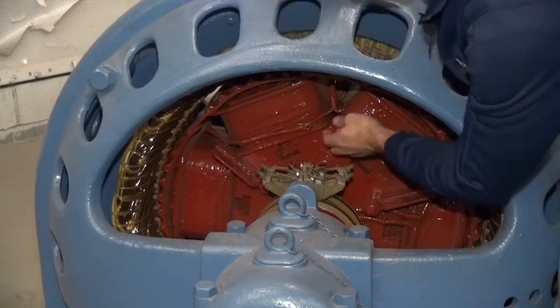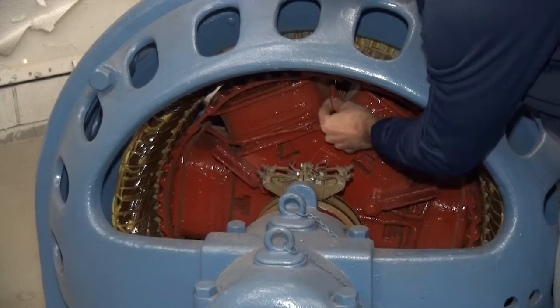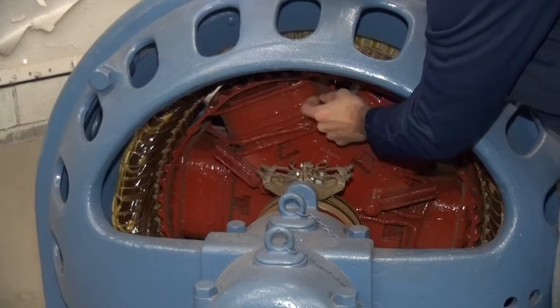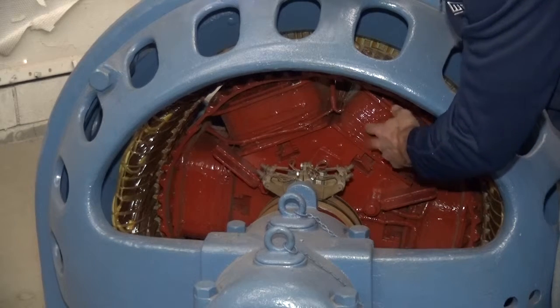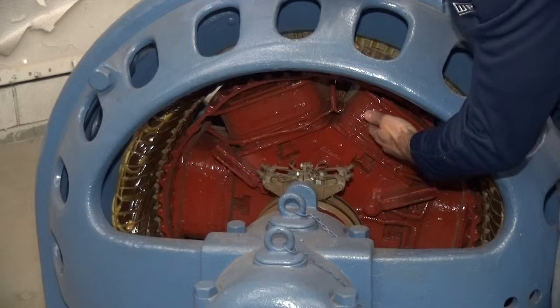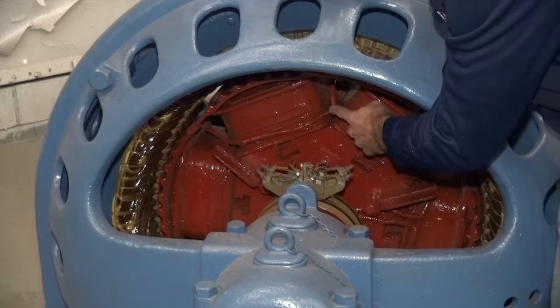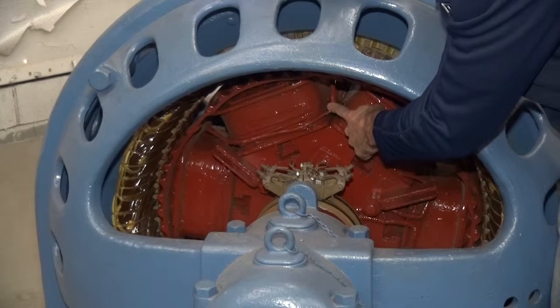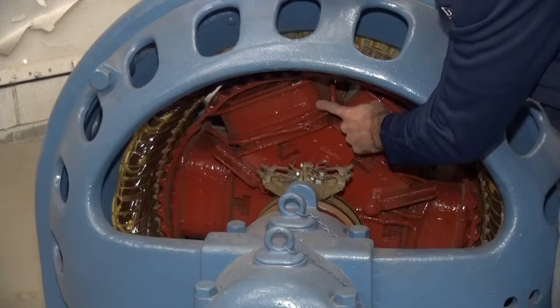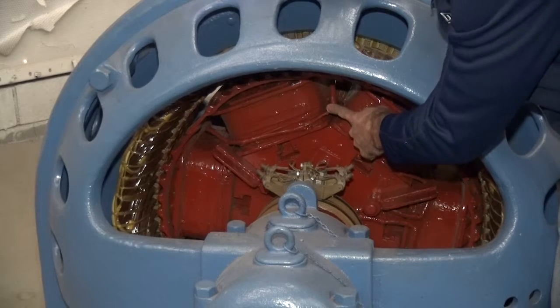You can also see that there are interpole connections. These are the cables in between each of the poles that pass the current from one pole to the other. And these are useful in doing a pole drop test and should be inspected because this is a location where a failure can occur.